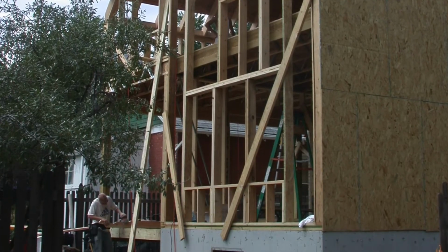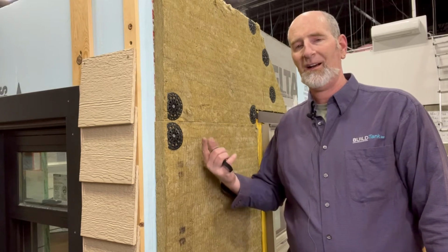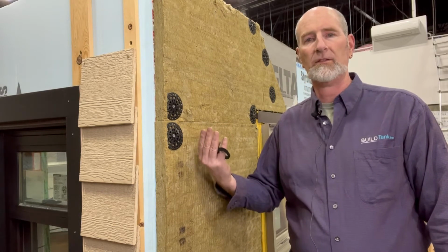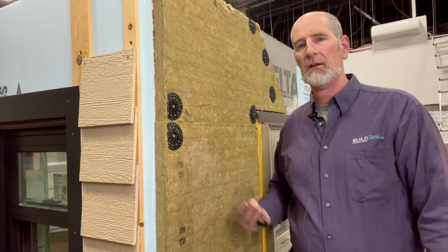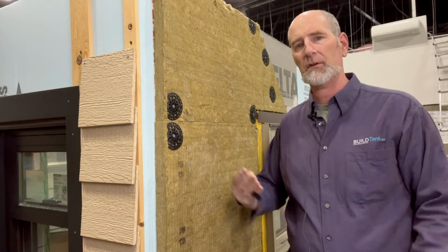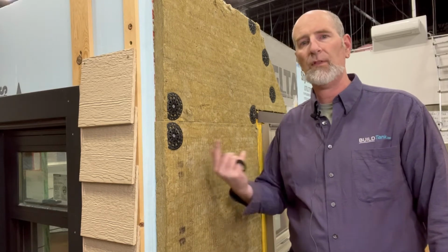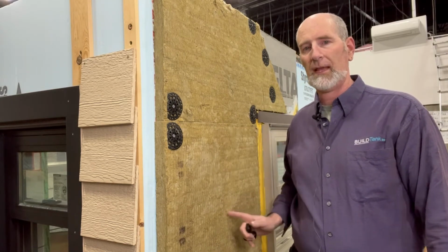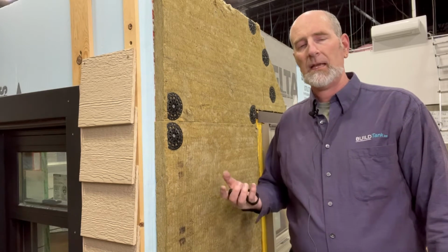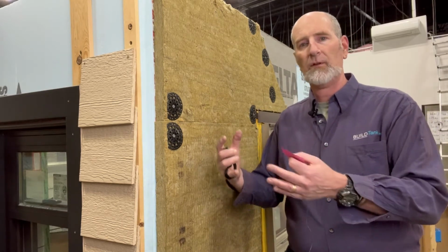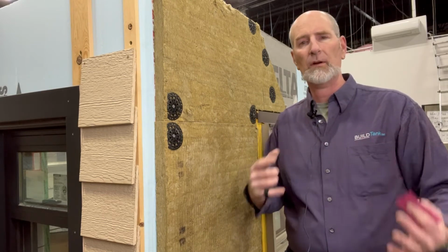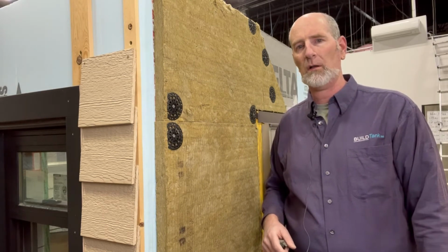The framing factor is what we're talking about. And wood has an R value of 1 per inch. Therefore, at each stud, I'm getting this additional energy loss from higher temperatures to lower temperatures, or higher concentrations of energy to lower concentrations of energy through that stud versus through the cavity there. So it takes my total wall R value from around R20 to about half that, 10, 11, 12, somewhere in that range is where the total wall R value is.